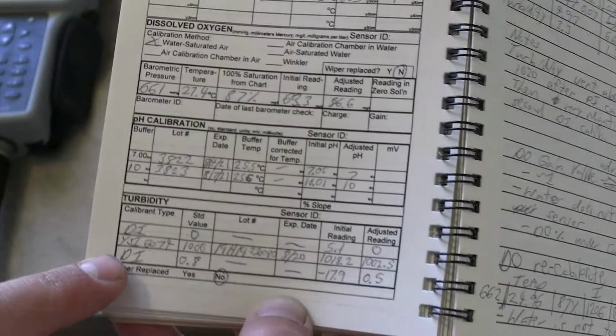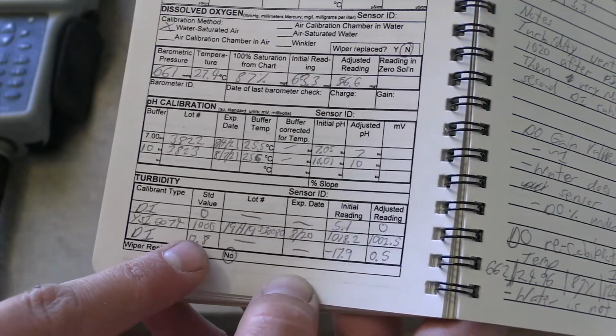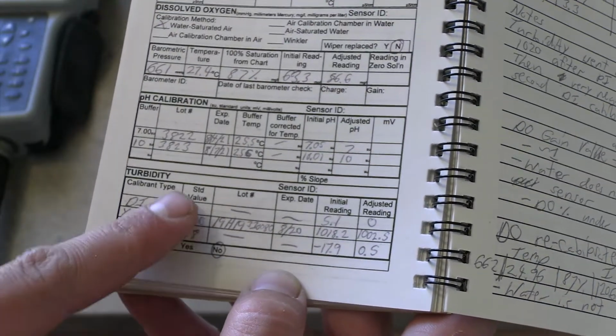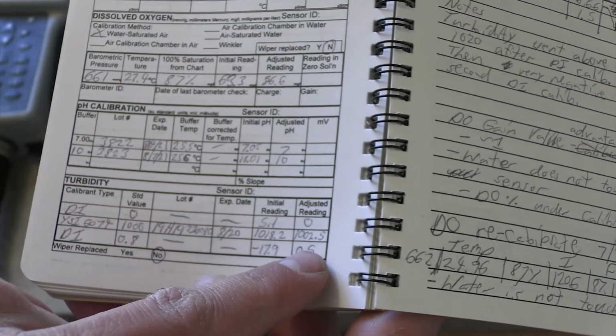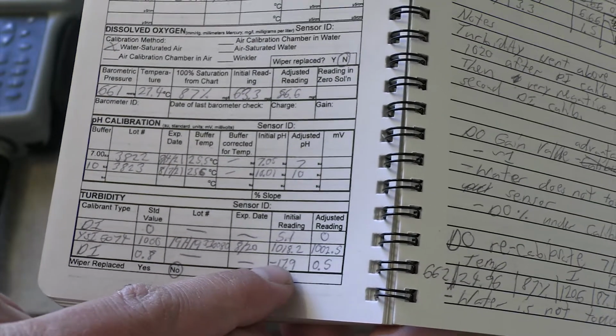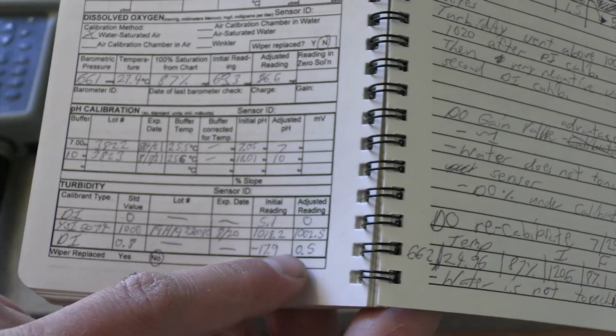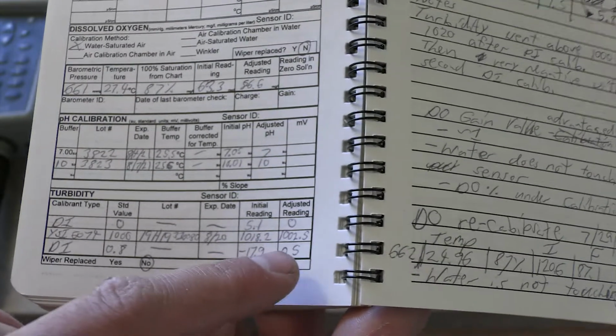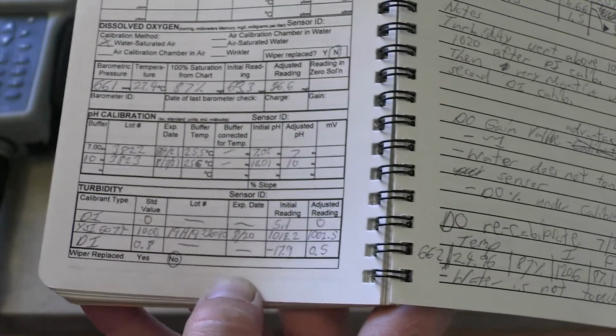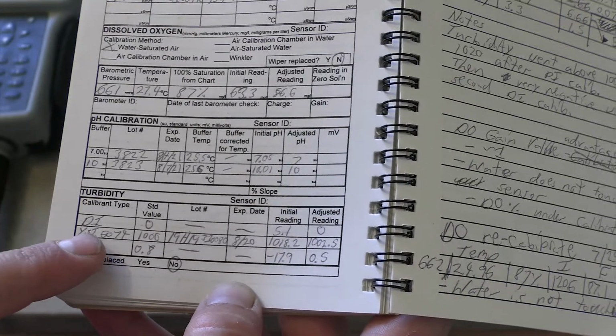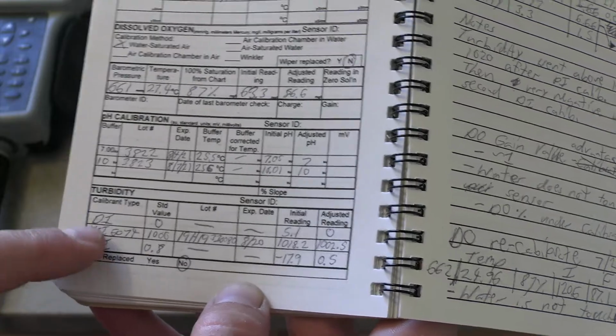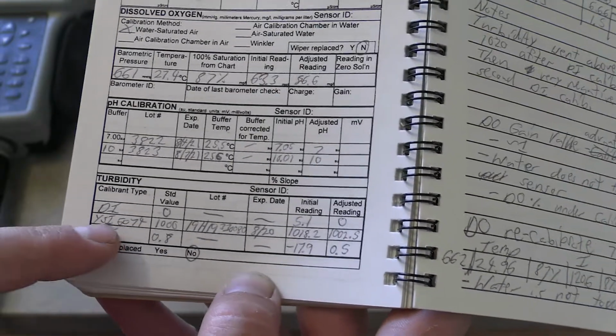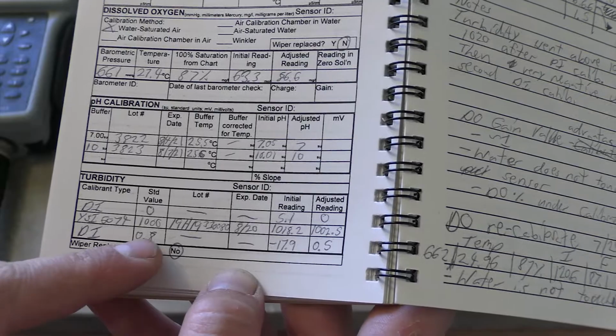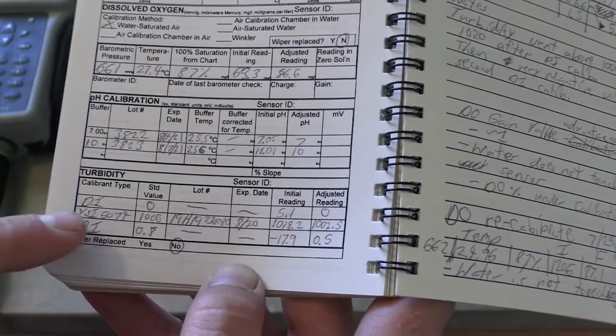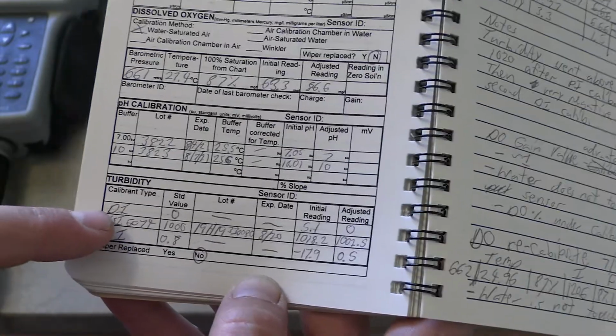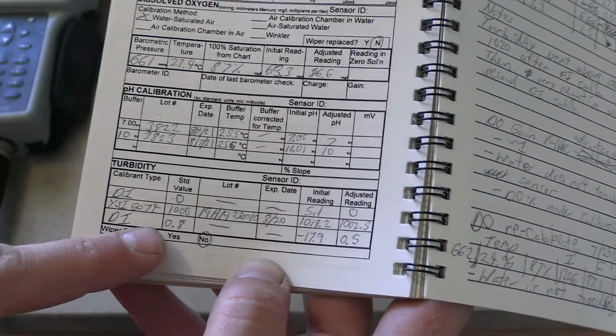And then you actually go back again with the DI water, and you do 0.8 and not 0, because if you do 0, what will happen is it'll go negative, and you don't want that. This is already negative here, and so you're actually recalibrating it above 0 to keep a negative from happening. But later on I've actually just skipped the first calibration and did a 2-point calibration, started with the solution and finished with DI water at 0.8, and it seems to work fine. So I would recommend just doing a 2-point calibration, starting with the YSI solution, and then finishing with DI at 0.8.